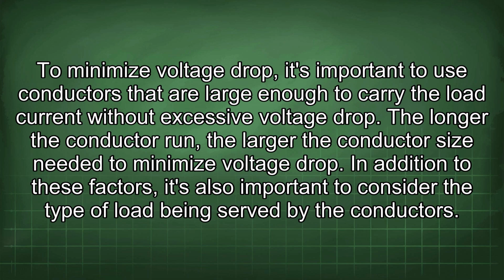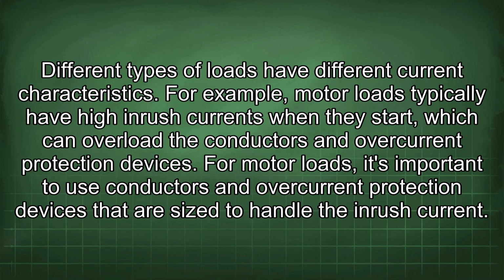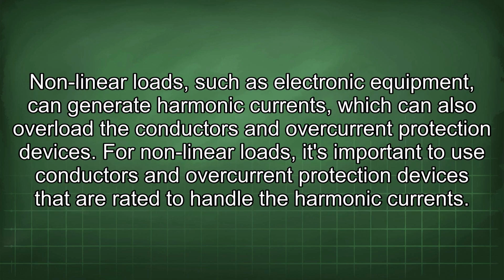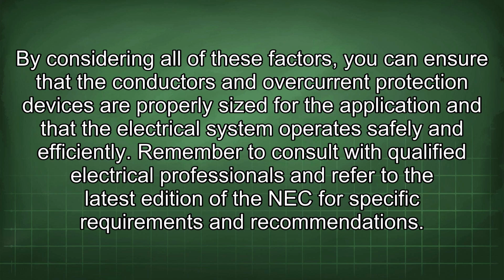In addition to these factors, it's also important to consider the type of load being served by the conductors. Different types of loads have different current characteristics. For example, motor loads typically have high inrush currents when they start, which can overload the conductors and overcurrent protection devices. For motor loads, it's important to use conductors and overcurrent protection devices that are sized to handle the inrush current. Nonlinear loads, such as electronic equipment, can generate harmonic currents, which can also overload the conductors and overcurrent protection devices. For nonlinear loads, it's important to use conductors and overcurrent protection devices that are rated to handle the harmonic currents. By considering all of these factors, you can ensure that the conductors and overcurrent protection devices are properly sized for the application and that the electrical system operates safely and efficiently.